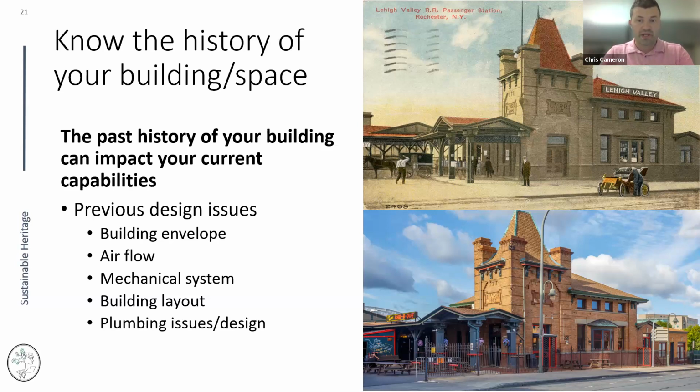Now they're using it for collection storage, and they can't achieve good collection storage conditions. It's because the mechanical systems were never designed to achieve that. And when they moved in, they cut corners, they did a lot of value engineering, we call it, and they didn't really upgrade things, and they're using older mechanical systems not designed for collections. So they're resulting in those issues.